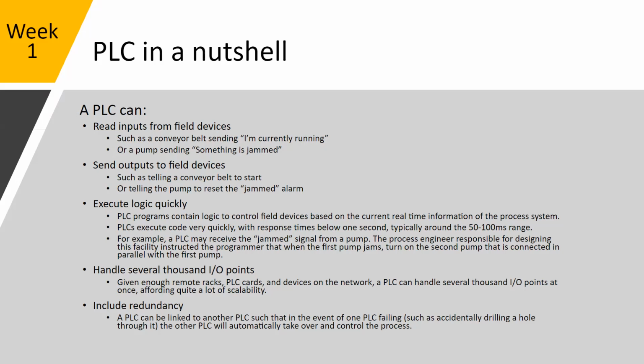They can execute logic. So the PLC programs contain logic to control field devices based on the current real-time information of the process system. PLCs can execute code very quickly. So this is the main difference between the DCS and the PLC, with response times below 1 second, typically in the 50 to 100 millisecond range. So for example, a PLC may receive a jammed signal from a pump. The process engineer responsible for designing this facility instructed the programmer that when the pump jams, turn on a second pump that is connected in parallel with the first one. So depending on the response times required, a PLC can do this very quickly.